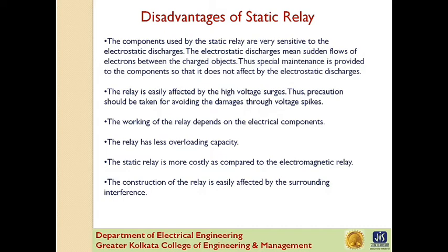Fourth, the relay has less overloading capacity. Fifth, the static relay is more costly as compared to the electromagnetic relay. And the last, the construction of the relay is easily affected by surrounding interference. For integrated protection and monitoring systems, programmable microprocessor controlled static relays are preferable.